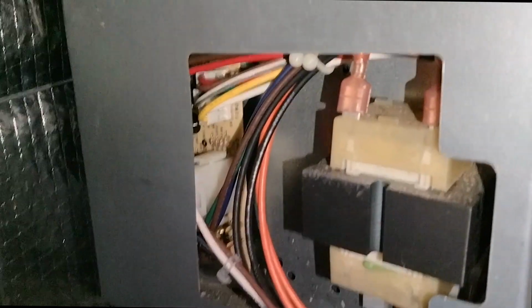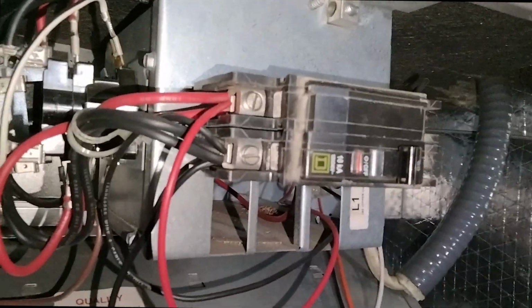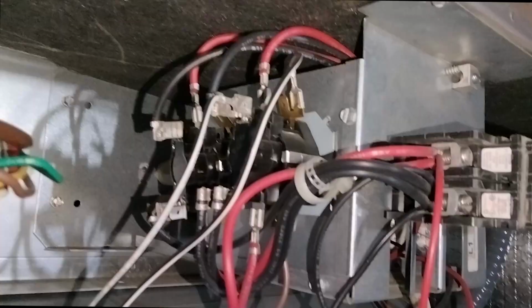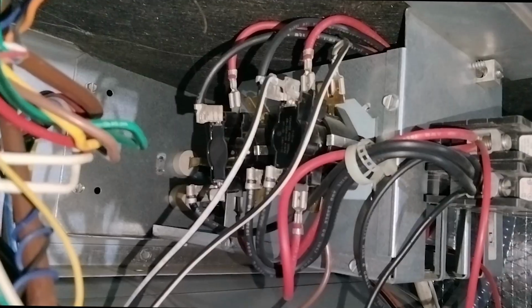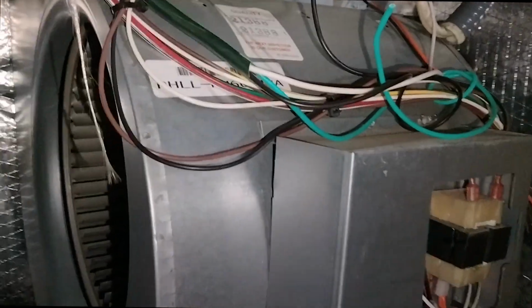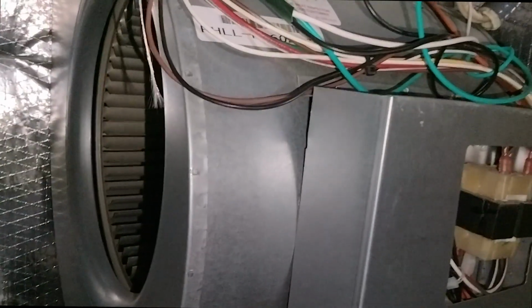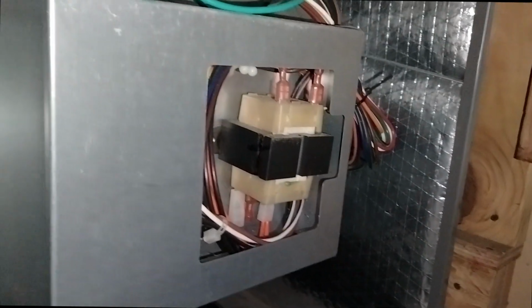Now this is going to have a fan control relay at this board right here. This is going to be your breaker here. Some of you might have a bunch of breakers in a row. You're going to have your sequencers, and yours can look different. They can be mounted on its side. You can have 3 stacks, you can have 2, and we do have a video on sequencers and testing them. Bottom line is, if your blower motor isn't even coming on in any setting, whether it's heat, cool, or fan on, the place to go for that first is to make sure, again, that you have power coming in.